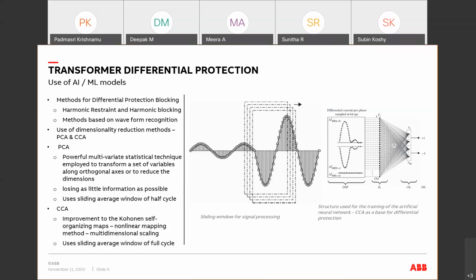The methods based on harmonic currents do not work reliably in cases where the differential currents show low harmonic content. Suppose the core of the transformer is a new magnetic steel core. The harmonic content will be so low that you will not be able to distinguish between the inrush current and the fault current when there is a fault. Transformer overexcitation is another possible cause of incorrect operation in a differential relay.